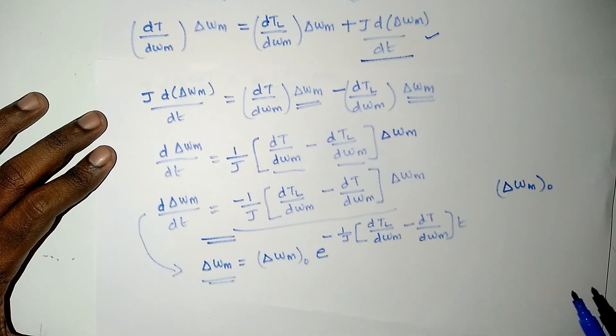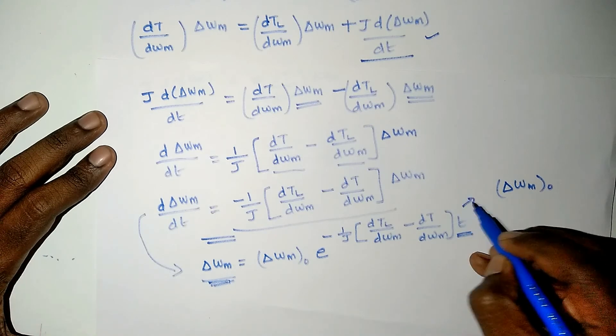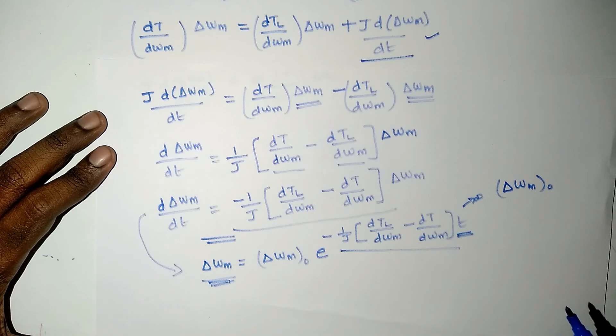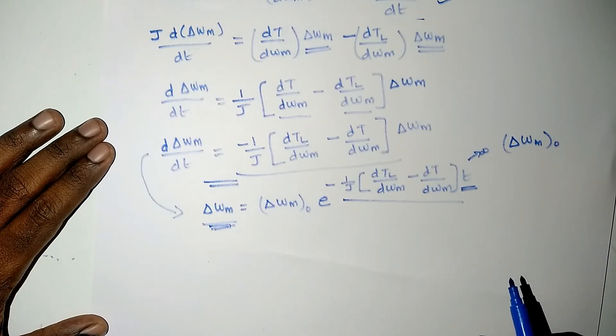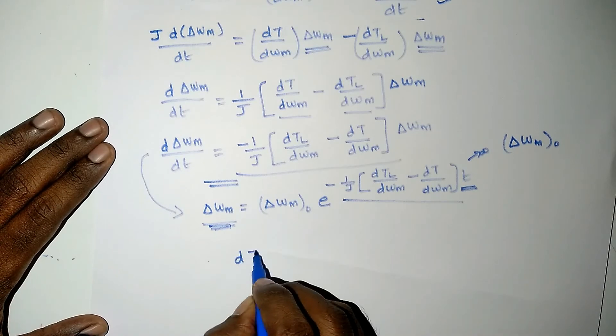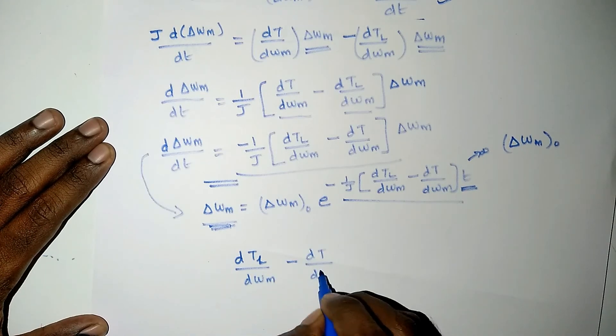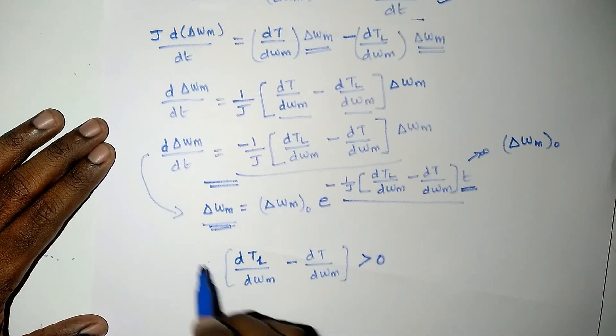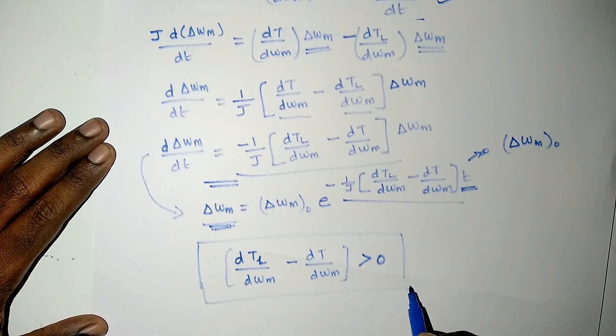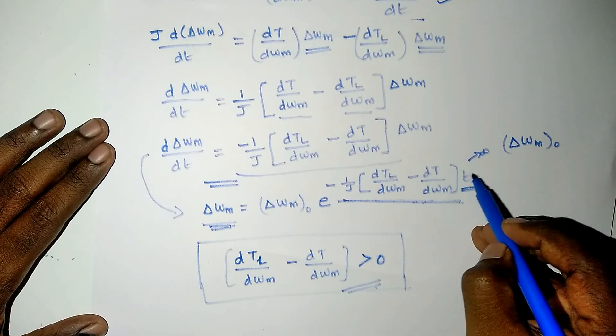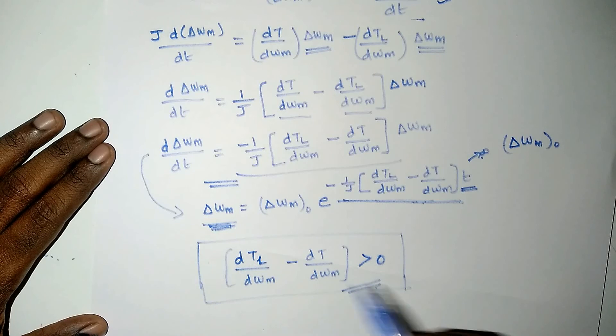The equilibrium point will be stable when delta_omega_m approaches 0 as time tends to infinity. For this to happen, the exponential term must be negative. Therefore, the condition for steady state stability is: dTL/d omega_m - dT/d omega_m > 0. If this condition is satisfied, the exponential term will be negative, and when t approaches infinity, delta_omega_m will become 0.